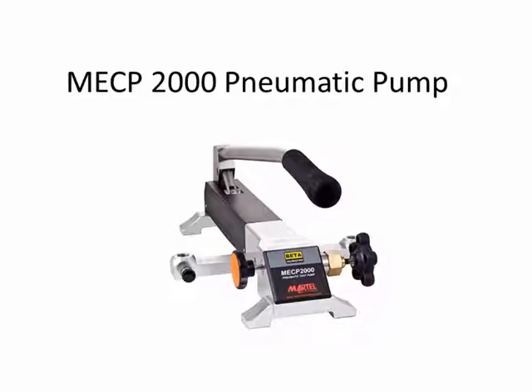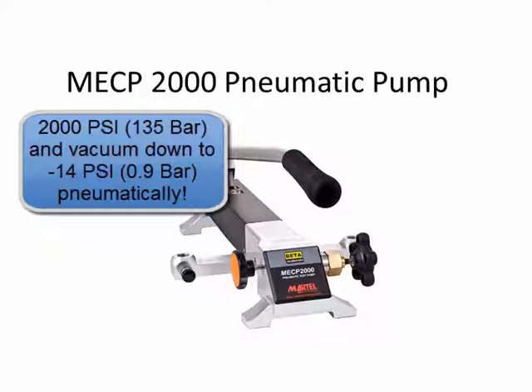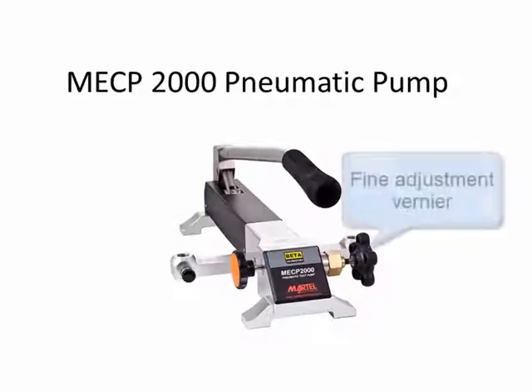The Martel MECP-2000 pneumatic hand pump is capable of generating pressures up to 2,000 psi and vacuum down to minus 14 psi at sea level. For very low pressures, the fine adjustment vernier can be used to generate precise pressures.